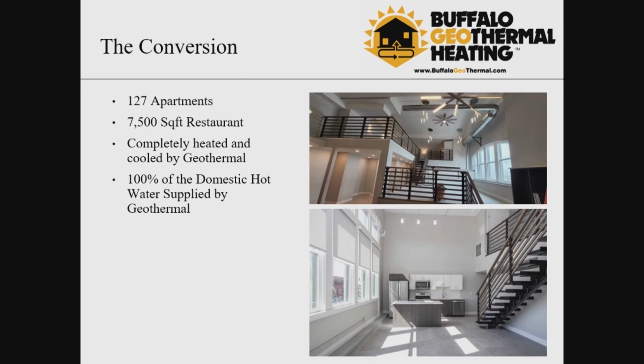In 2017, developer Dr. Greg Daniels started to gut rehab this building and converted the 158,000 square foot structure into 127 loft apartments and a large future restaurant spanning 3 stories high under that concrete barrel roof. The geothermal system that we designed and installed provides the space conditioning for all apartments, the common spaces, 100% of the domestic hot water, and it also has enough spare capacity to take into account the future restaurant of the building.